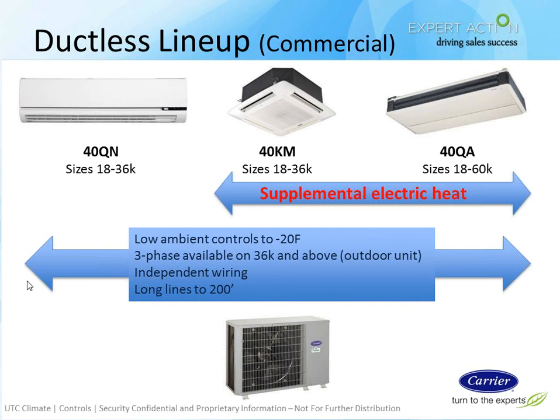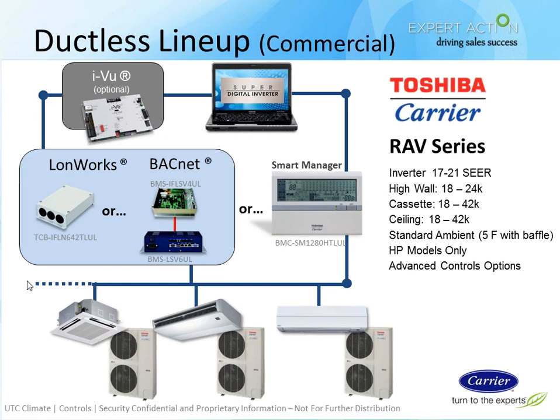Of note, the 40KM, that ceiling cassette that you see up in the middle, is being phased out. So we do have good inventory for that unit. So if you need that, please get them while you can. We will eventually run out of those, but we will support it parts-wise and tech support-wise as well. Another advantage of the Carrier ductless split systems is that it's easier to integrate into our Carrier controls platform.